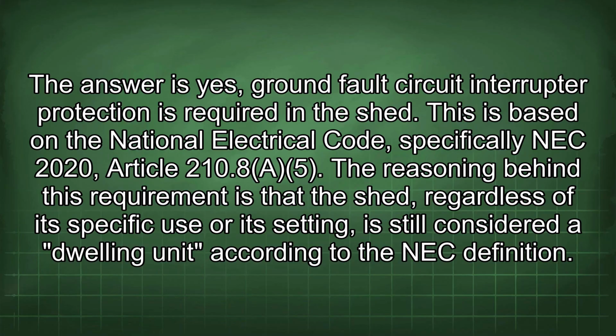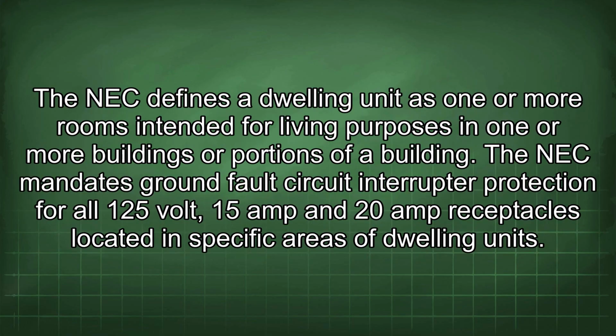The answer is yes, ground fault circuit interrupter protection is required in the shed. This is based on the National Electrical Code, specifically NEC 2020, Article 210.8(A)(5). The reasoning behind this requirement is that the shed, regardless of its specific use or its setting, is still considered a dwelling unit according to the NEC definition. The NEC defines a dwelling unit as one or more rooms intended for living purposes in one or more buildings or portions of a building.